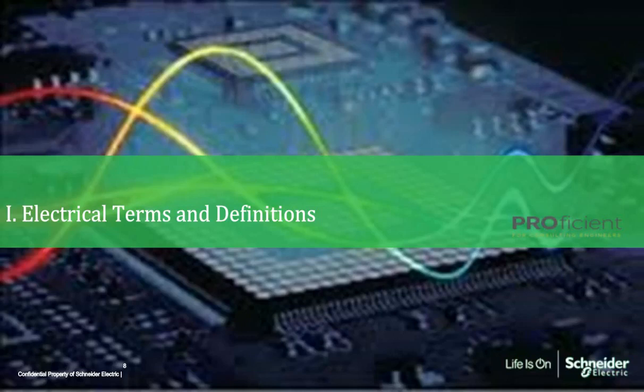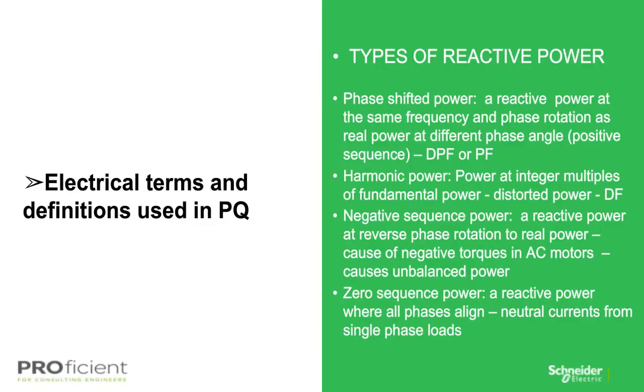Moving next to further types of reactive power. First, we have phase shifted power, which can be leading, typically caused by capacitors, or lagging, caused by inductors. This always occurs at the fundamental frequency, typically 50 to 60 hertz, and is commonly defined as the displacement power factor, also known as DPF. And this is typically what the utility charges penalties for, again, depending on your local utility and your geographic location within the U.S.